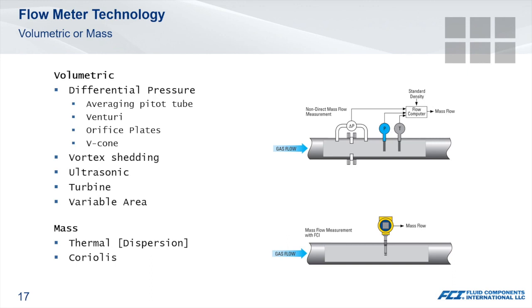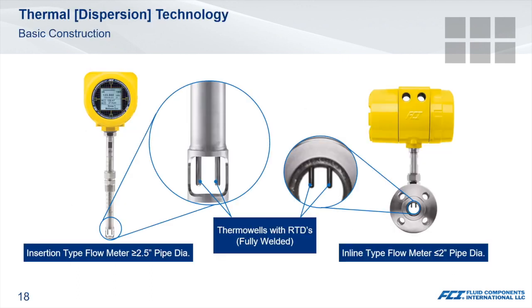Volumetric flow meters require additional pressure and temperature instrumentation for compensation. This adds some complexity that impacts your total cost of ownership. Mass flow technologies such as thermal and Coriolis eliminate costs associated with the initial purchase and longer-term maintenance. Let's look at the basics of a thermal flow meter and better understand its operating principles and how it accounts for changing gas densities.